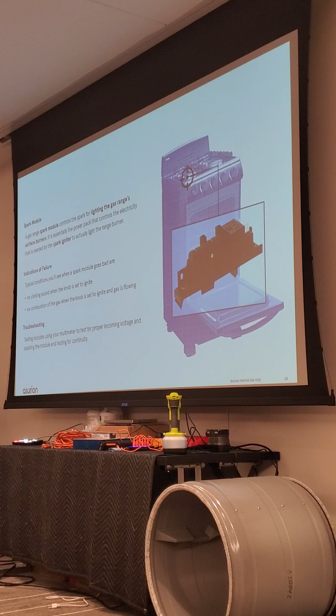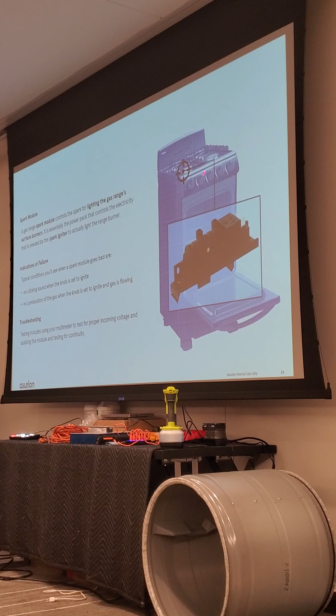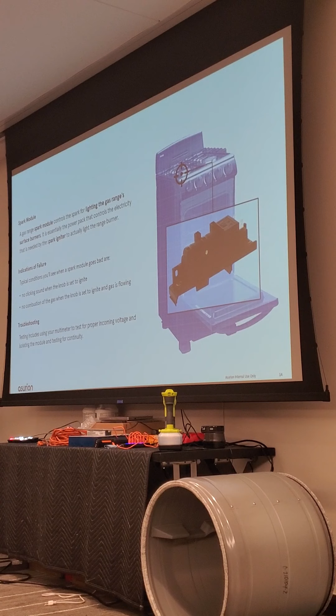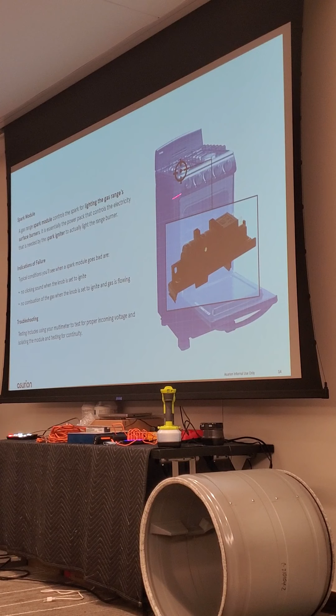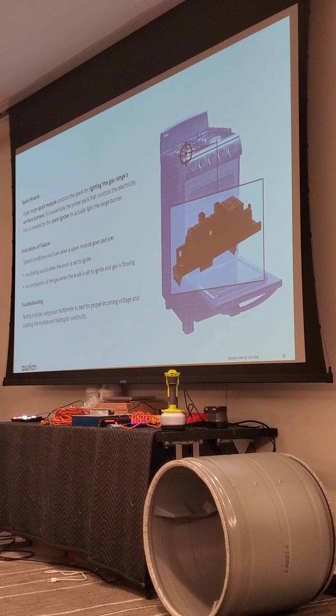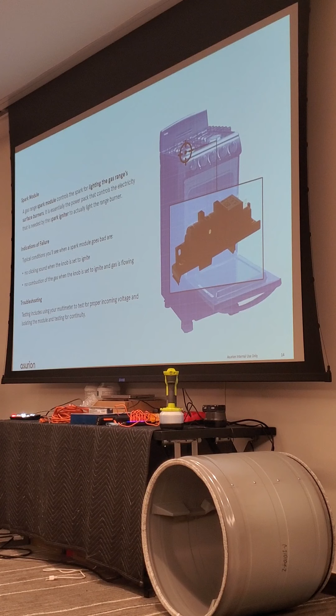Typical failures: no clicking sound, no combustion from the gas, set to ignite, and the gas is flowing. Okay, but you can take a manometer or a magnehelic and actually test the gas flow on these. Usually that's about 4 inches of water column, so about 4 is what you need for these to properly work. Testing includes using a multimeter, going to voltage, isolating the module, and testing for continuity. Again, continuity is not a complete check. I always say check with ohms.